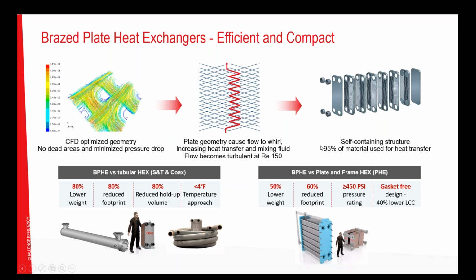So the heat exchanger is very material efficient, with about 95% of all material going inside used for heat transfer. So this means that the brazed plate compared to the tubular type of heat exchanger is much more efficient, with more turbulence, more energy transfer per weight, per size, per everything. So for the same efficiency, you will have at least 80% lower weight, at least 80% reduced footprint, at least 80% reduced hold-up volume with a very close temperature approach.